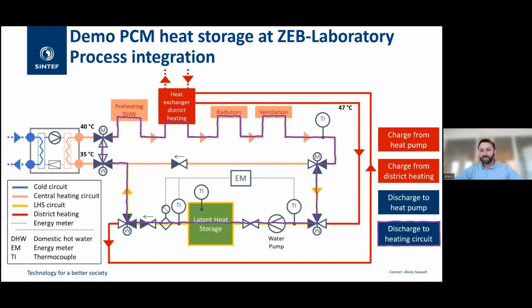We have 2 ways to look at the state of charge. We have the regular temperature measurement at different places in the tank, and that will tell us a bit what's going on. Of course, it's not always isothermal in every part of the tank, so we can have a good follow-up on that. But the best measurement we have is always the energy meter on the outlet and inlet of the heat storage. So we know constantly the temperature and flow of the water going in, and the temperature of the water going out. So it's pretty accurate, actually.